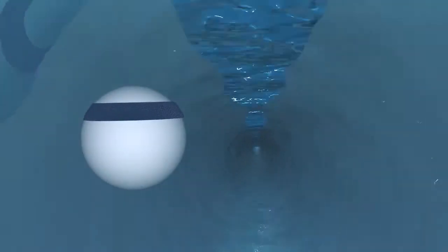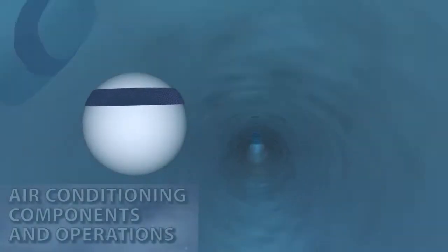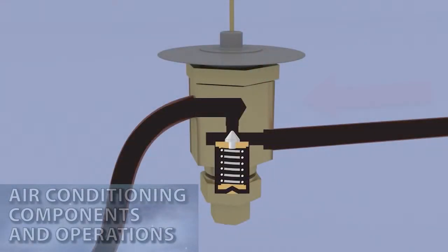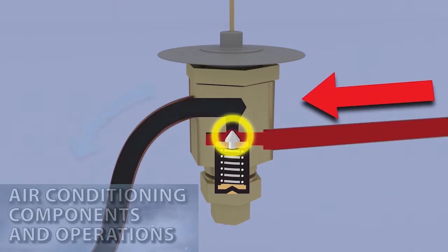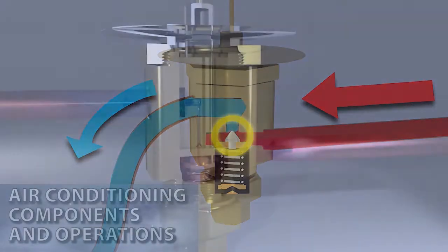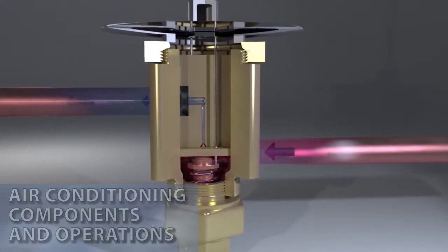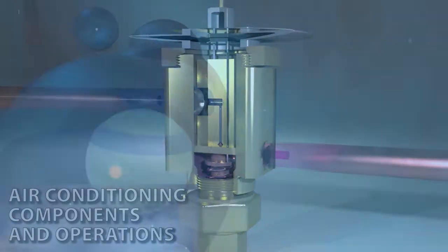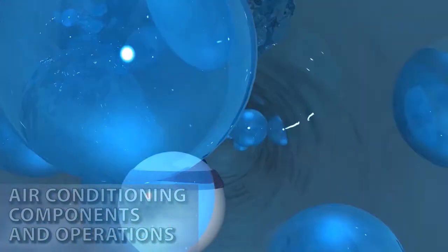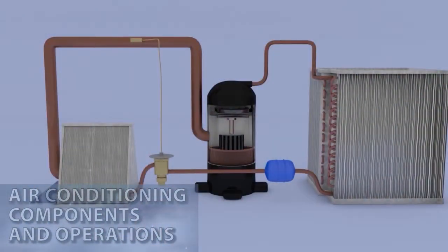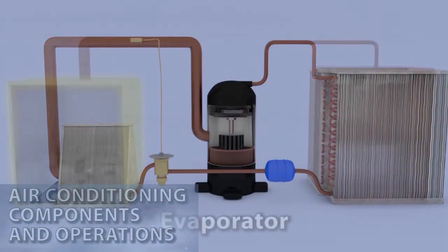The cooler refrigerant liquid enters a small refrigerant line to return to the evaporator. To complete the cycle, the liquid is reduced in pressure by a small orifice and starts the evaporation cycle again. This pressure-dropping orifice is needed to help lower the pressure above the refrigerant. As long as the compressor runs, the cycle continues. This is the cooling cycle in its simplest form.